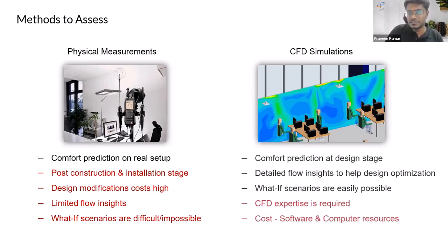On the other hand, with CFD simulations, you can predict the comfort at the design stage itself. You get detailed flow insights throughout the space - it's like having an infinite number of sensors installed in your conditioned space, giving you the complete picture at the design stage. So you can simulate what-if scenarios, play with different design configurations, move the supply and return locations, play with the CFM, play with the system, whether it's VAV or CAV. All those things you can simulate at the design stage.